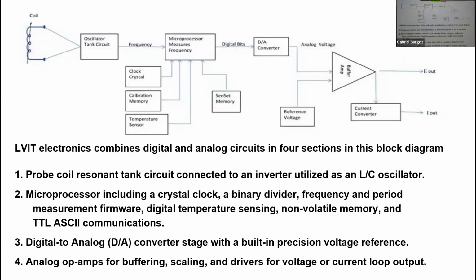It stores information because, in this case, unlike an LVDT where it says linear, the linear applies to two things. One, as you saw in that V curve, you get a straight line on the output, so it's linear in that sense. But also the core moves in a linear fashion, a straight line, as opposed to curvilinear.